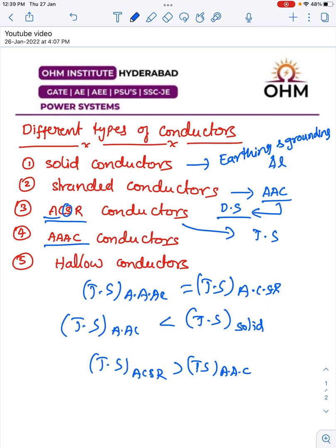What is the main advantage of triple AC conductors? First, the disadvantage: the cost of triple AC conductors is high when compared to ACSR conductors. But triple AC conductors have the same tensile strength as ACSR conductors. The main advantage of triple AC conductors is that they are lightweight. Because of this lightweight construction, these conductors are suitable for both transmission and distribution for special applications — not for all applications, only for special applications.